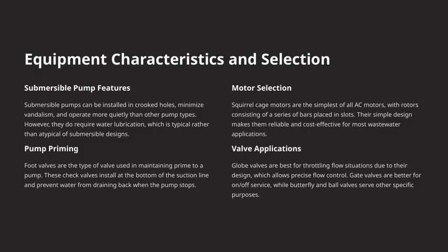Now, let's take a closer look at some key equipment characteristics and how to select the right components for our system. Starting with submersible pump features, these pumps are quite versatile. They can be installed even in crooked holes, which gives us more flexibility during installation. Plus, they help minimize vandalism since they can be placed in secure, less accessible locations. One of their advantages is that they operate more quietly compared to other types of pumps, making them ideal for locations where noise reduction is important. However, it's important to remember that they do require water lubrication, which is typical for submersible designs, so proper water supply is essential for their operation.